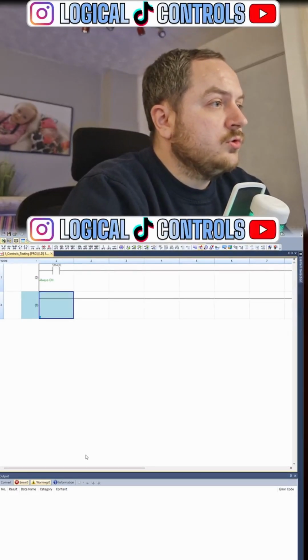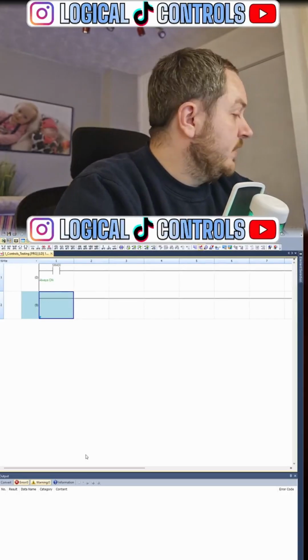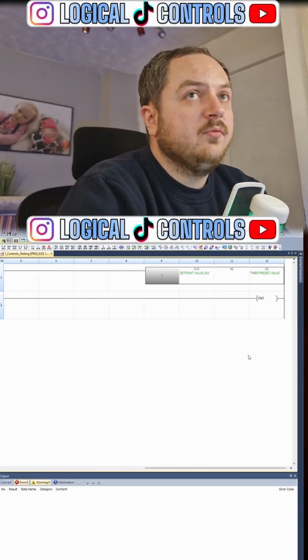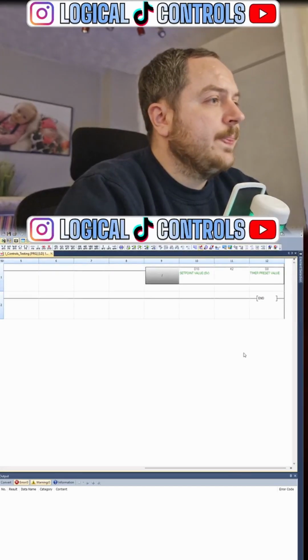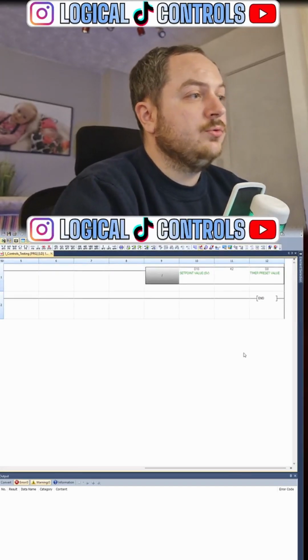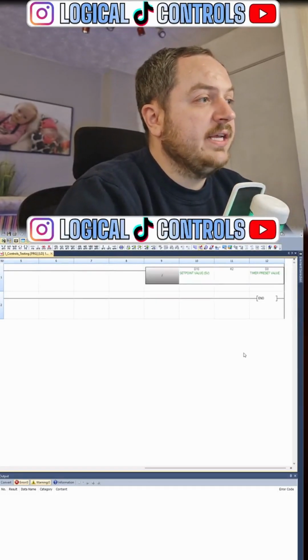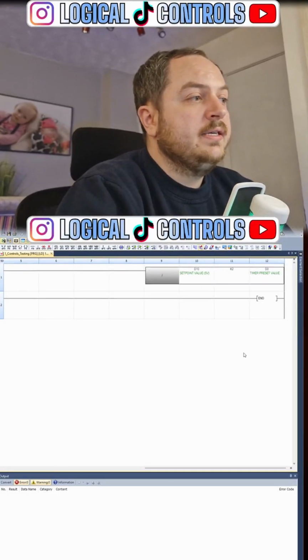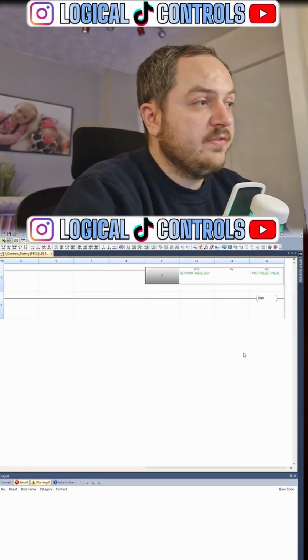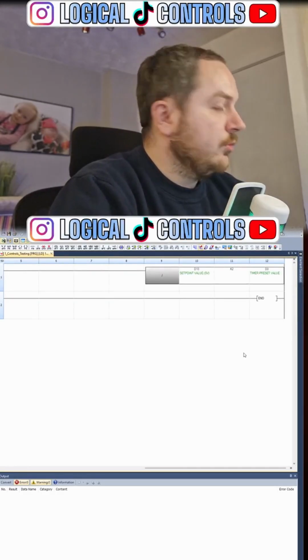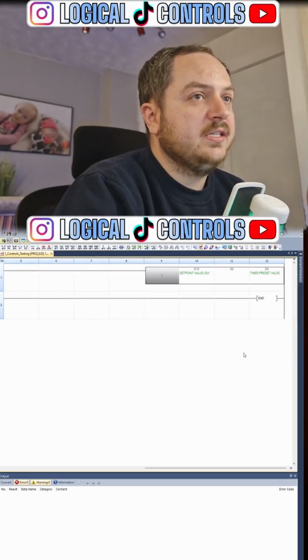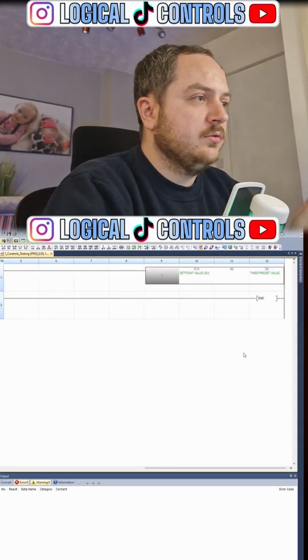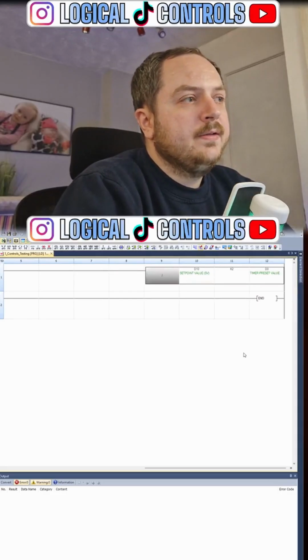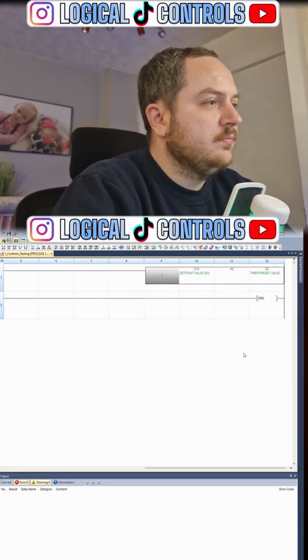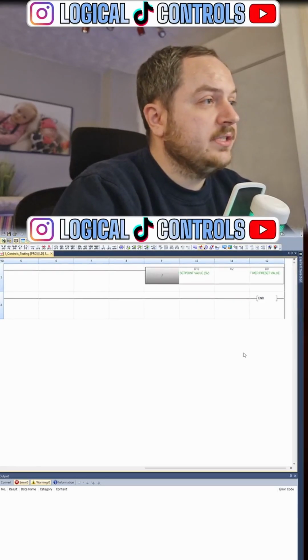Can it handle 120 volt through its relays, or all on board relays 24? No, it can, yeah, you can put 230 volts on them relays. I would never recommend doing it. What is the recommended way to do it is you slave the outputs off to separate relays, individual relays. The reason you would do that is because if you had a fault on whatever you're driving, whatever your output is, you don't want it to ruin a relay output on that very expensive device. You'd rather it ruin the relay that you're slaving it off to. Because you can have a very bad day if you start welding output relays and that sort of thing on the PLC itself.